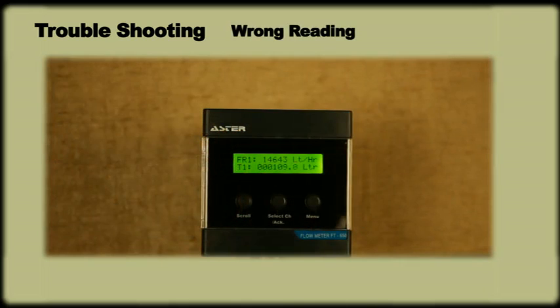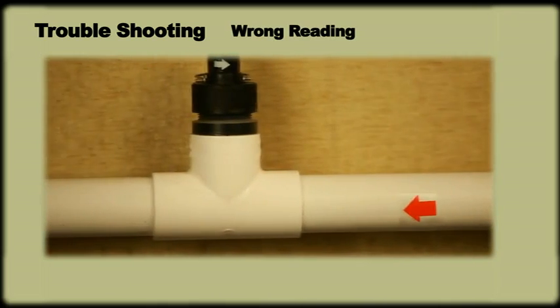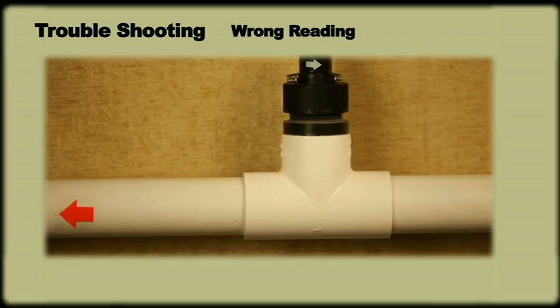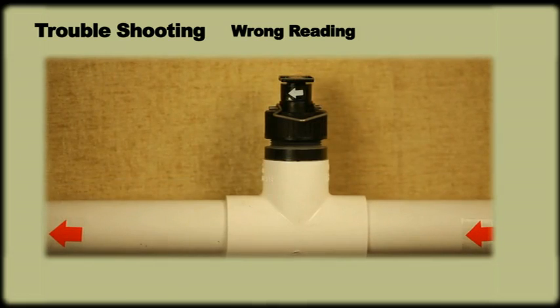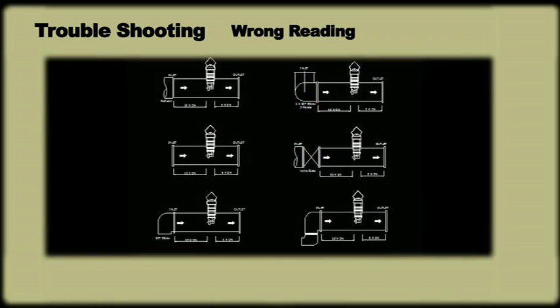If the meter shows error in reading, it could be because of the following reasons. Check the direction of the arrow and see if it is in the correct orientation. If adequate straight run is not provided at upstream and downstream of the sensor, then provide straight run as per guidelines.